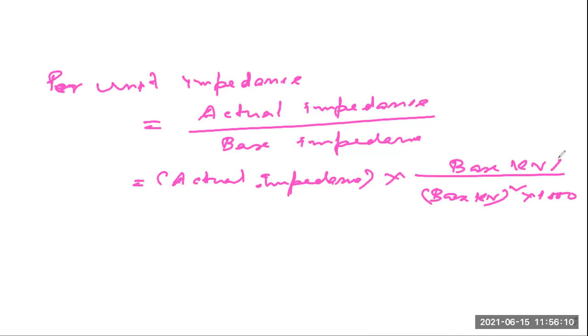Sometimes it may be required to use this relation in reverse. Sometimes the actual impedance in ohm is required. This is a simple arithmetic calculation. Actual impedance in ohm means per unit impedance into base kV square into 1000 by base kVA. So this formula you should remember. This is a very, very important thing. When you do the calculations, these formulas will actually be required. You should know this formula.